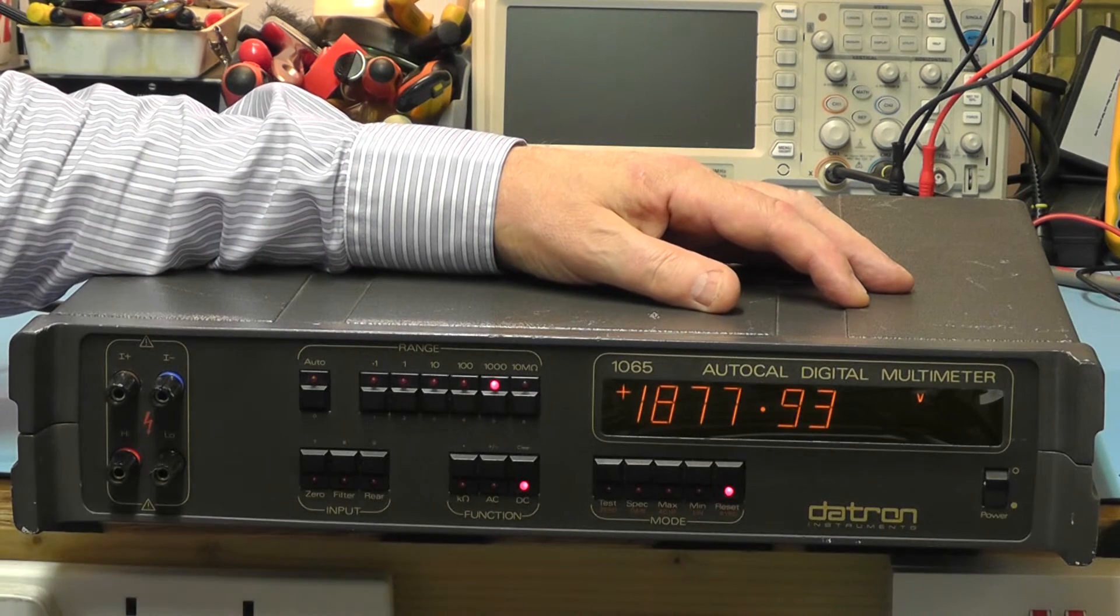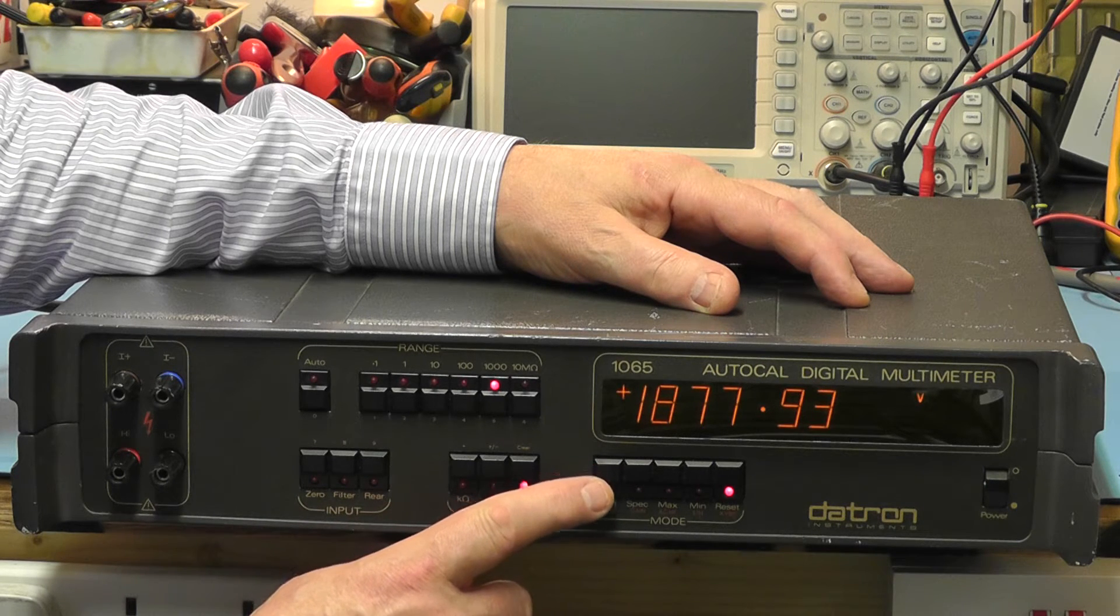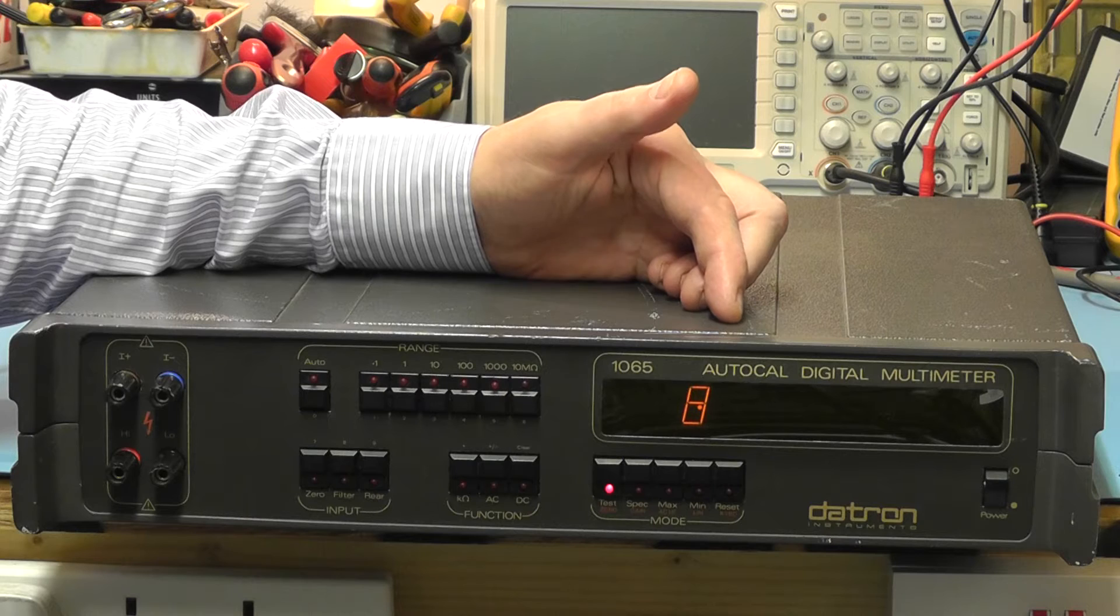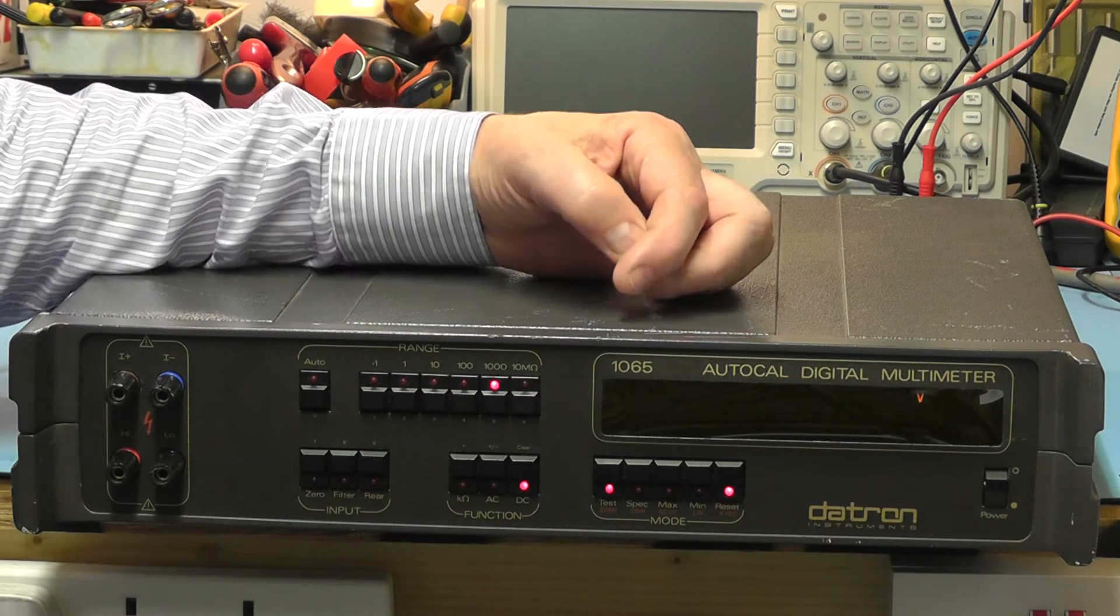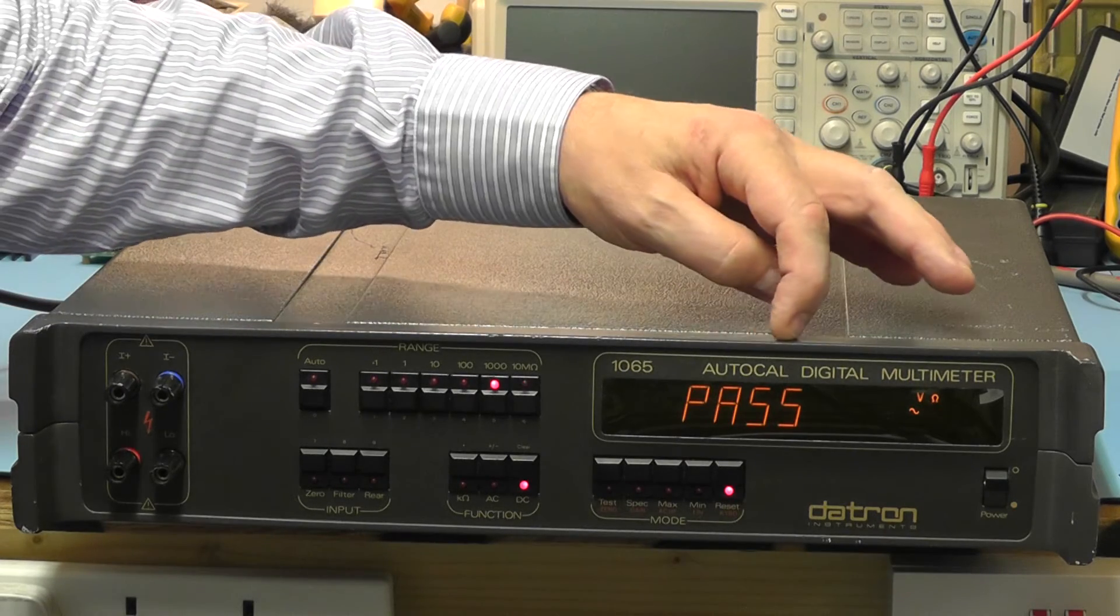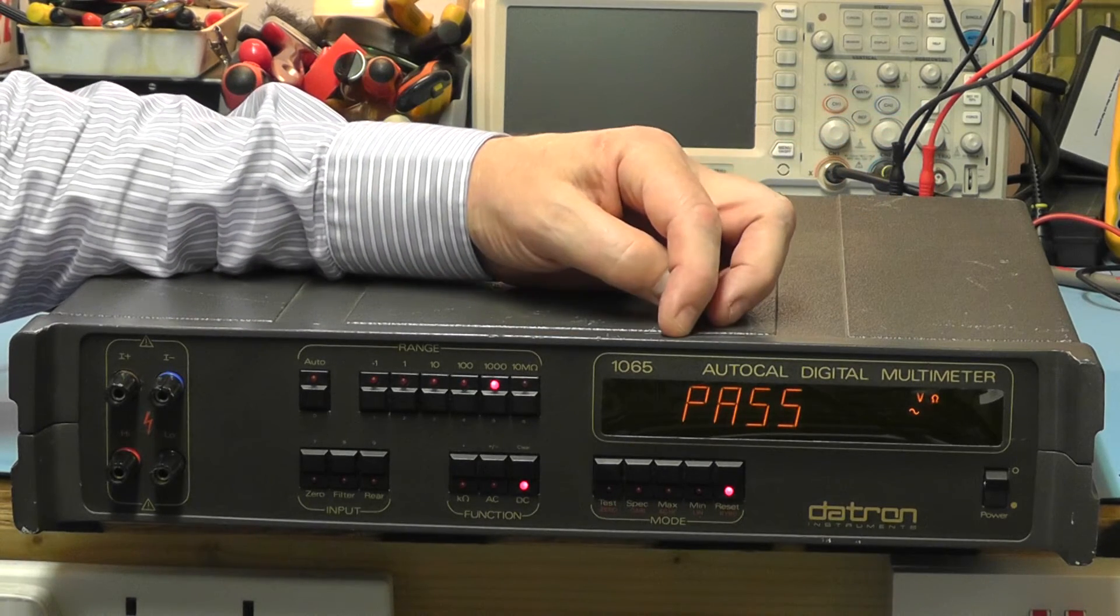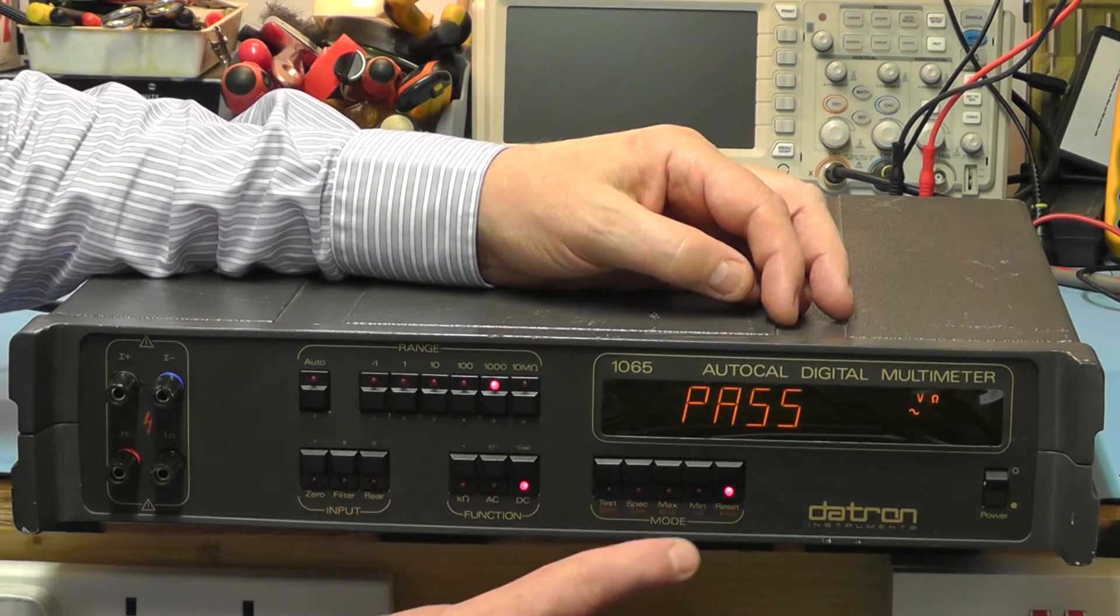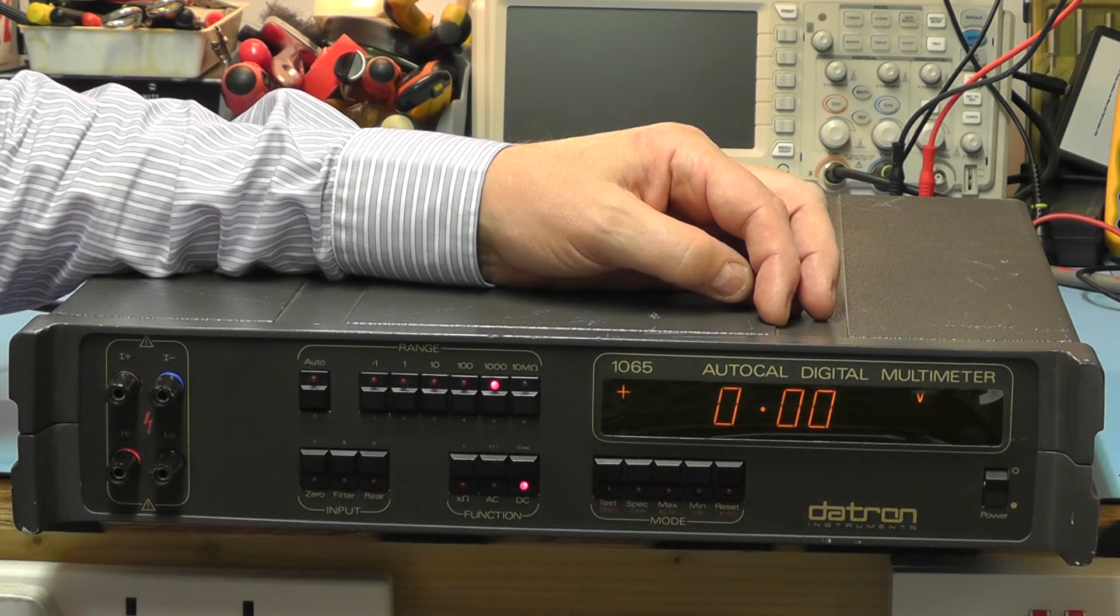The meter has a test function. Here we have the test button on the front of the unit. If I press that you'll see it go through the test sequence. It's first of all testing the display, all the segments of the display. You then go through another test sequence testing the other parts of the instrument and if you pass it comes up with a pass remark on the display. If there was an error with the meter you'd get an error code showing on the display. To come out of the test mode simply press the reset button and that returns the meter back to normal function.